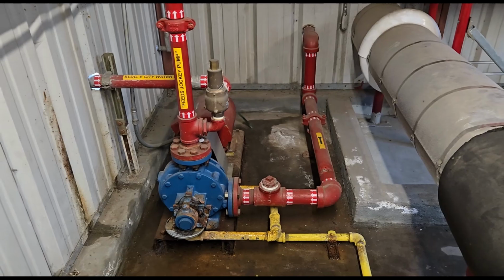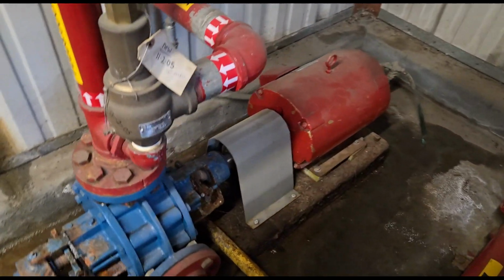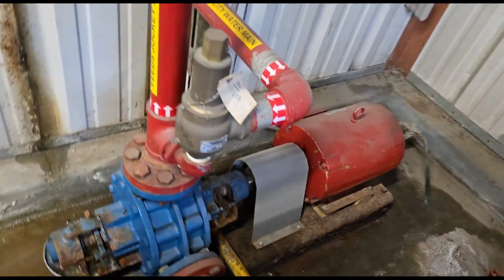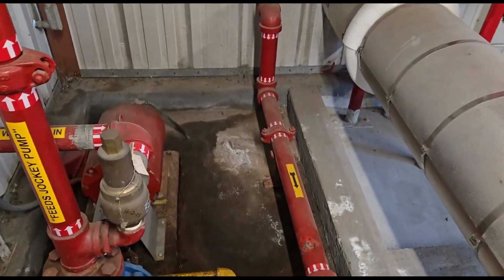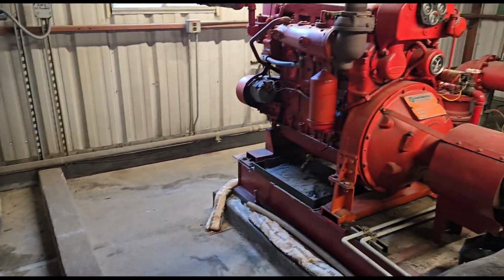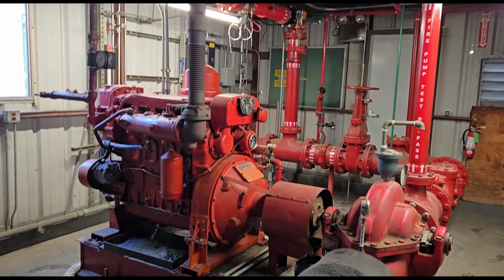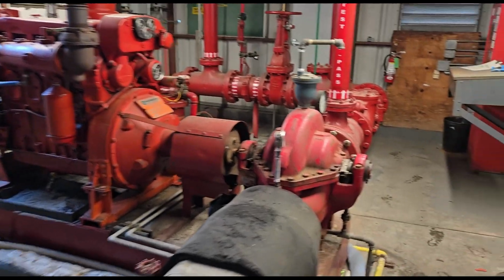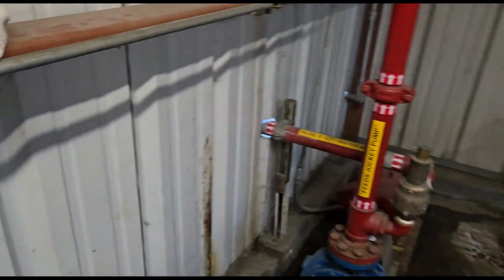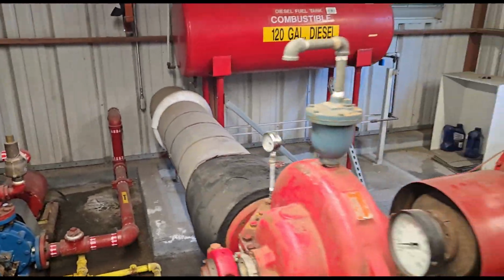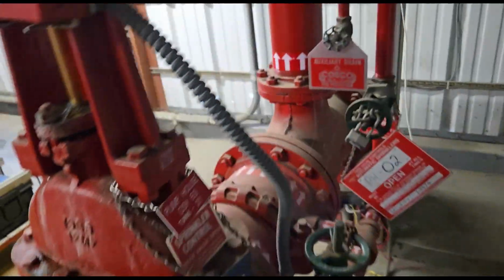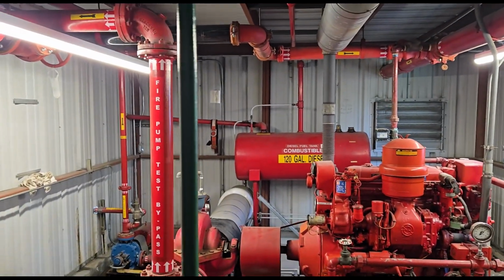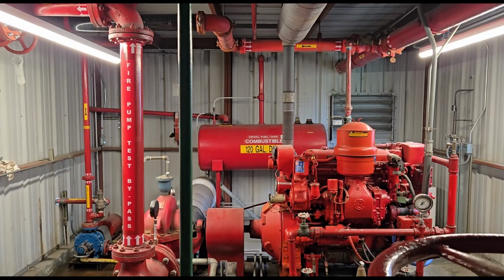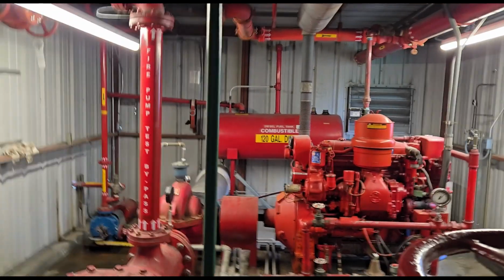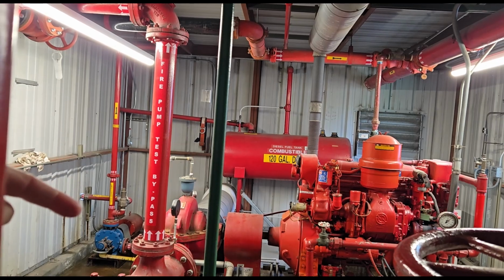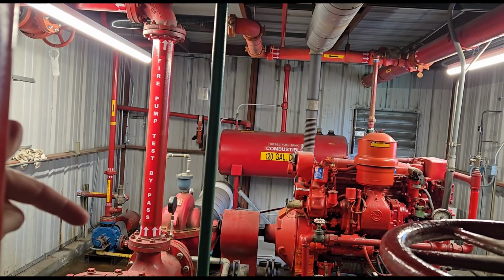All right, we have our jockey pump running. Little guy right here. So while the water is flowing, it is keeping pressure, and the main pump here is not on, so it does not kick on. So we have that turned off. All the work is being done by this little jockey pump. And for a little comparison, you can see the big pump turned off here, and the little guy turned on right there. So this is doing all the work for our flow testing.